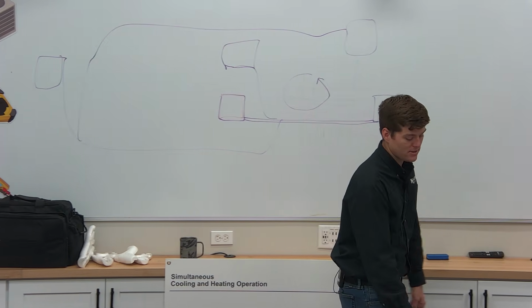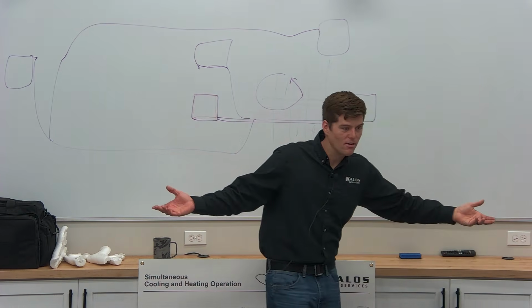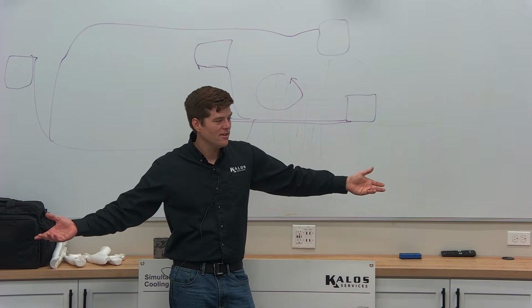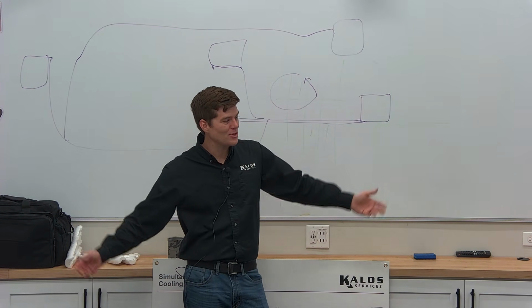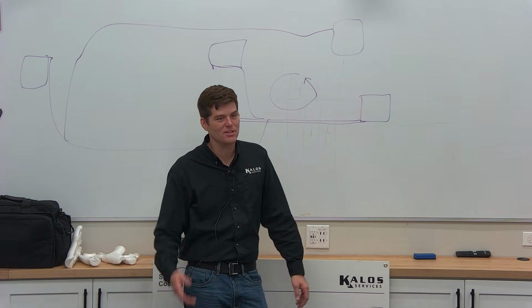And Lord forbid it's a room that they don't ever use anymore. It never comes on. You get 50% of your system's oil trapped in a line to an indoor unit because these weren't followed.